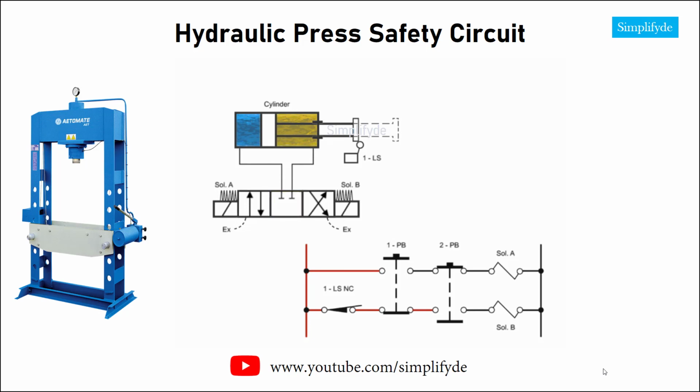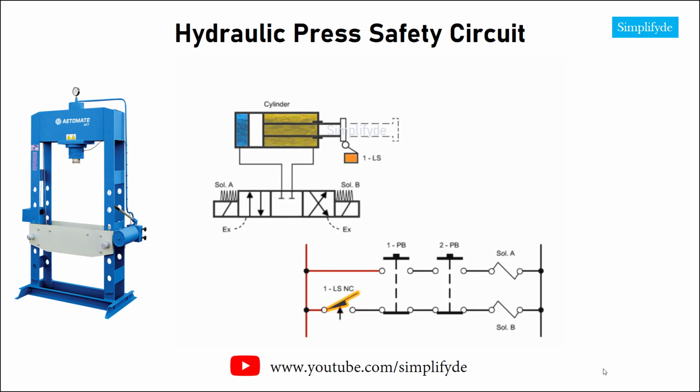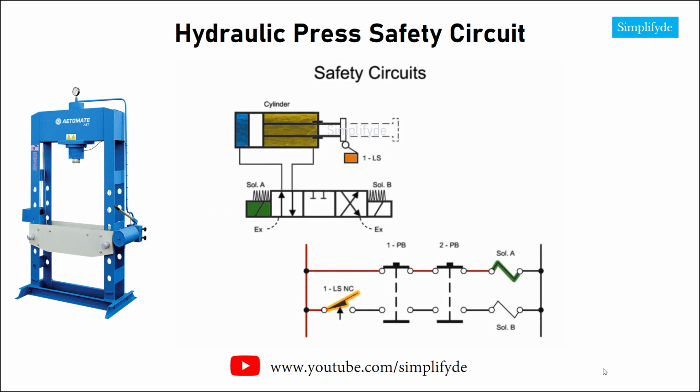If both buttons are released while the cylinder rod is extended, limit switch 1 allows solenoid B to become energized. The valve will shift to allow fluid into the rod end of the cylinder, causing it to retract. When it reaches the end of its stroke, it engages the limit switch, which opens the circuit and prevents electricity from flowing until the two start buttons are engaged once again. If both buttons aren't released, the cylinder cannot move back to its starting point to restart the cycle.